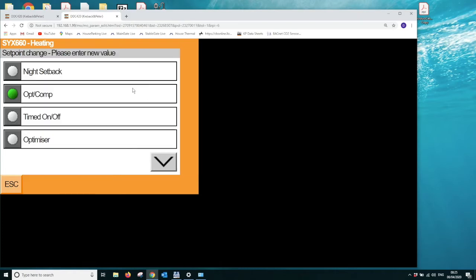The options in there are night setback. This would be something I would select for something like a care home or something with 24-hour occupancy, something like a hotel or something where there is a constant heat demand, something like a fire station maybe, where we just throttle the heating by a reduced level throughout the nighttime period. Timed on off, obviously that's exactly as it sounds.